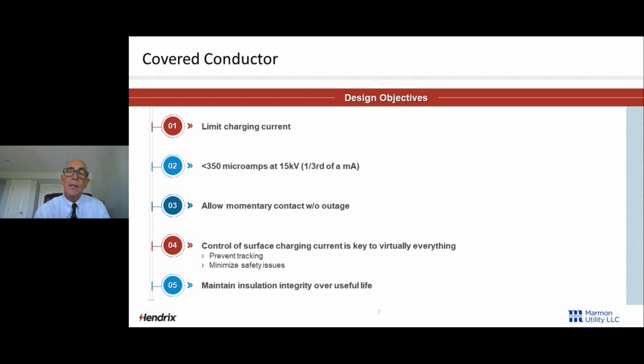Now that 1/3 of a milliamp is going to hurt. It's going to give you a shock, but it's only 3, 4, 5% of the fibrillation current. So you can certainly let go, and you will let go quickly. And if you're in your right mind, you won't grab it again. So it's not safe, but it's certainly not fatal. That 1/3 of a milliamp on that jacket is going to allow momentary contact without an outage.